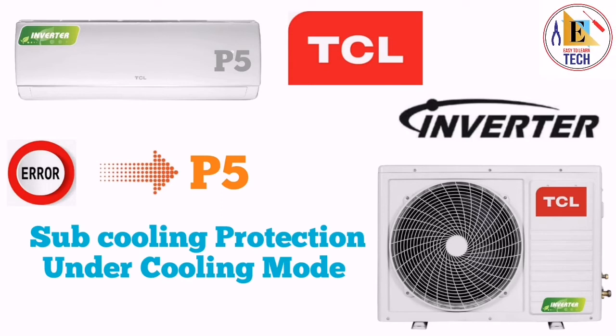You have to check both the ends of these two sensors, if it is showing 5 kilo ohms or not. If it is not showing 5 kilo ohms, replace the sensor, and if it is showing 5 kilo ohms, then you have to replace the indoor control board and your unit will be in working condition.